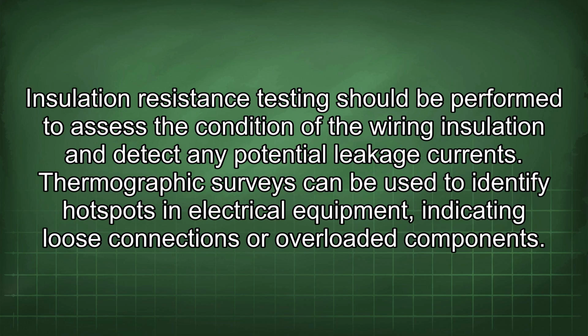Visual inspections should be conducted to check for damaged wiring, loose connections, and corroded components. Insulation resistance testing should be performed to assess the condition of the wiring insulation and detect any potential leakage currents. Thermographic surveys can be used to identify hotspots in electrical equipment, indicating loose connections or overloaded components.